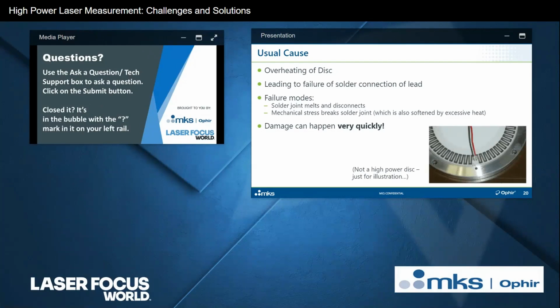Now, sometimes the overheating can be bad enough that the solder connection completely breaks, and then you've got sudden sensor death, the drop down to 0. Sometimes it becomes unstable. It might disconnect, but only partially, and then when the sensor cools down, it reconnects, only to disconnect again when it heats back up again with the next exposure to laser power. So the disease is the same, the symptoms might look a little bit different.